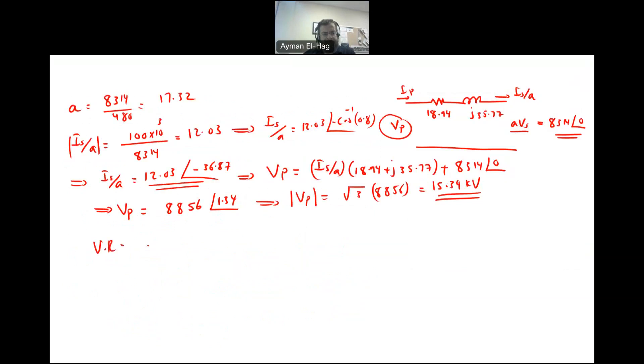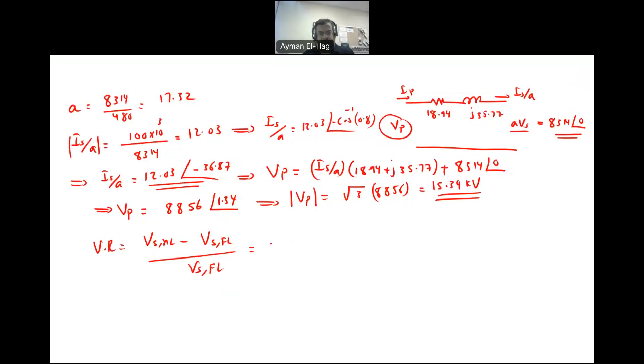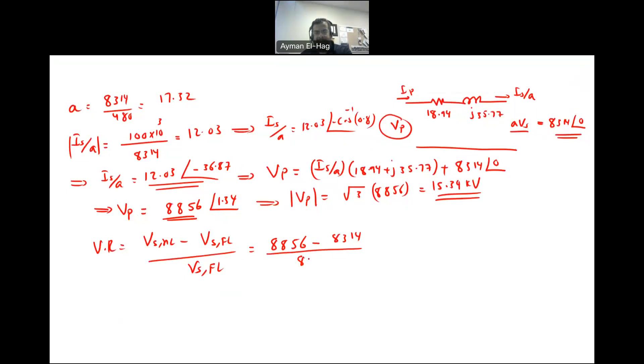Now for voltage regulation: it equals the secondary voltage at no-load minus the secondary voltage at full load, divided by the full-load voltage, times 100. Using single-phase voltages, this is (8856 − 8314) divided by 8314, times 100, which gives a total voltage regulation of 6.52%.